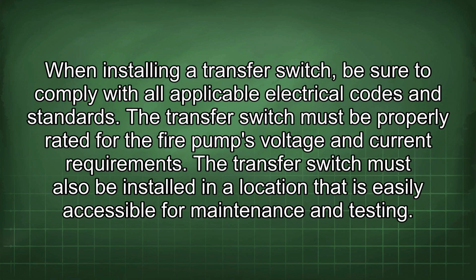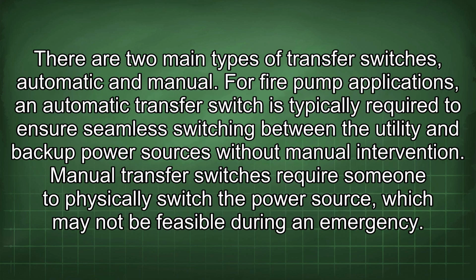When installing a transfer switch, be sure to comply with all applicable electrical codes and standards. The transfer switch must be properly rated for the fire pump's voltage and current requirements. The transfer switch must also be installed in a location that is easily accessible for maintenance and testing. There are two main types of transfer switches, automatic and manual.